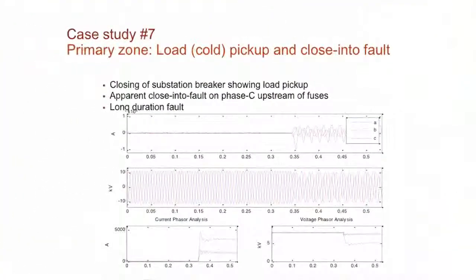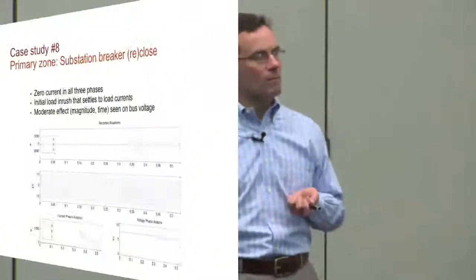But what do you see as a big delta? If you look at that picture just from the 10,000 foot level, what's the biggest difference? Is there any kind of load? You think there's any load there? It's zero. So that's a reasonable estimate that the breaker is actually open at the substation head, and then it closed. And when it closed, it picked up the load from the non-faulted phases, and then happened to reclose back into a fault, so it must have been a permanent fault.